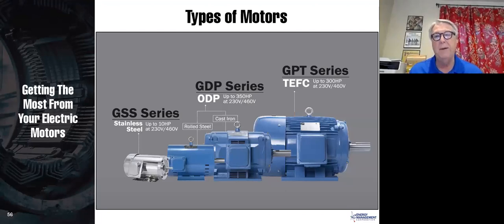All right, I want to talk a little bit about motor quality. Let's just look at these 3 motors. That's a rolled steel motor. So in a rolled steel motor, we just take a piece of steel, we wrap it in a cylinder, and then we shove the motor inside of it. That is the cheapest kind of motor. The flow of air goes through the motor, so any particulate in the air, oil droplets, whatever, are going to accumulate. You're going to end up with a dirty motor there, even in a fairly clean environment. So these are only suitable for clean environments. And even in clean environments, I would tend to not use them, although they're okay on smaller horsepower sizes.